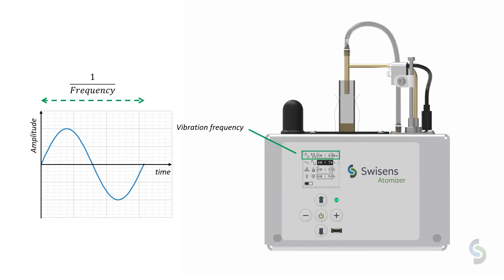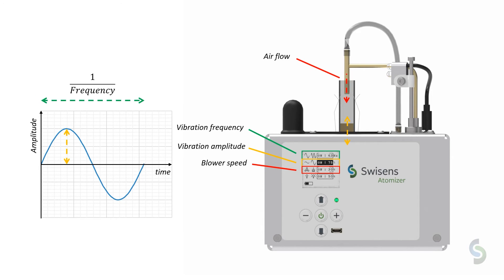Frequencies in the order of 50 Hz have been found to perform well for particles with a size of a few 10 µm, such as pollen. To control the number of dispersed particles, the vibration amplitude can be changed. Larger values — meaning a longer pathway the cuvette travels per vibration cycle — typically cause more particles to be aerosolized, thereby increasing the particle concentration. Another setting to control the aerosolization efficiency is the air blower speed, which changes the amount of air blown into the cuvette and in turn picks up particles.